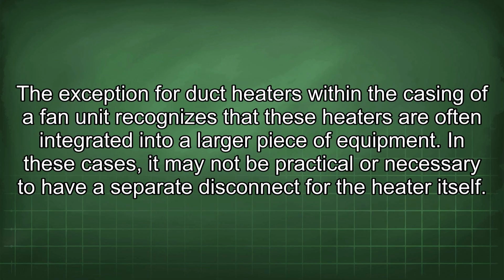The exception for duct heaters within the casing of a fan unit recognizes that these heaters are often integrated into a larger piece of equipment. In these cases, it may not be practical or necessary to have a separate disconnect for the heater itself.